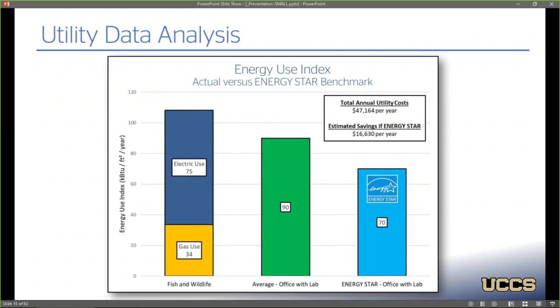So one of the main high-level analysis tools you can use is looking at the EUI, or energy use index, or energy use intensity, which looks at the building on an energy use per square foot basis, and this allows you to compare the building in question to another similar building in the same region and get an idea of how that building is performing. So I used the Energy Star Target Finder tool to see what an Energy Star certified office building might use, and the target EUI for that type of facility was about 60.